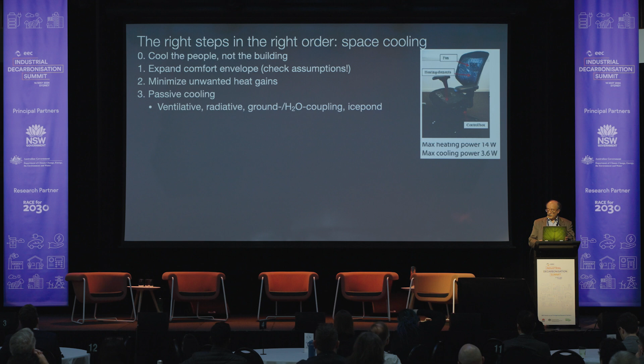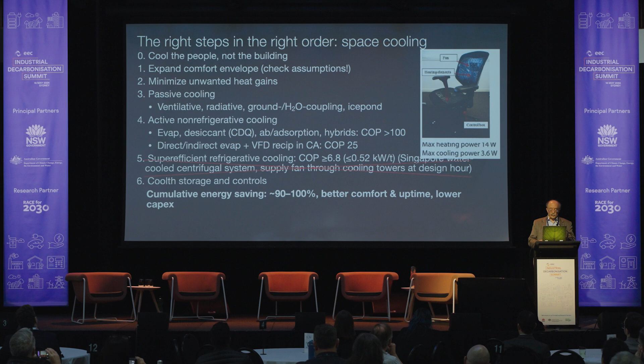Therefore we don't need other passive options, nor active non-refrigerative cooling that can yield over 100 units of cooling per unit of electricity, nor refrigerative cooling, nor fancy storage and controls. Even in the most severe climates, this whole system approach can save 90 to 100% of cooling energy with better comfort, lower capex, and higher uptime, without reaching step 5 or usually even step 4. Yet most practitioners pursue these options in reverse order, worst buys first.